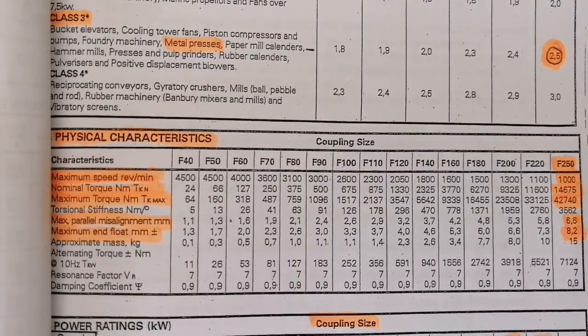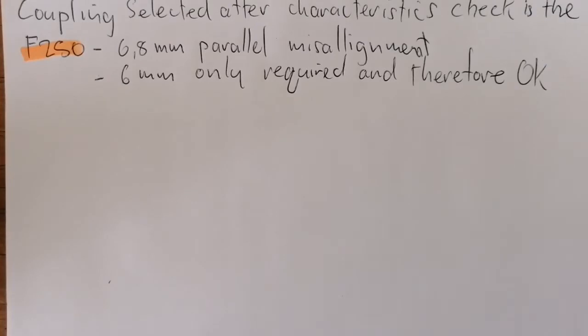The coupling selected after the characteristic check is the F250. The 6.6 millimeter parallel misalignment that it can handle is more than what is required, which is 6 millimeters, and therefore it's okay.